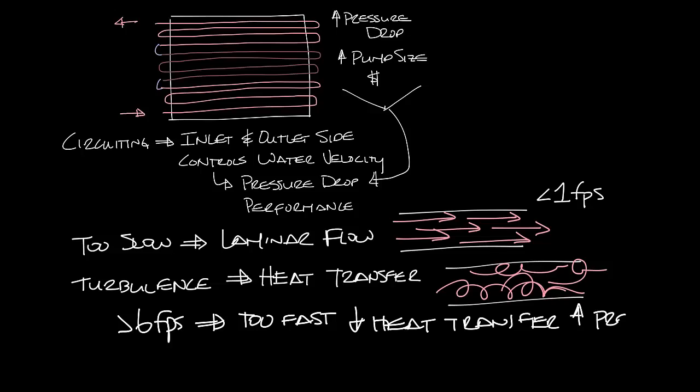This also significantly increases the pressure drop across the coil. So ideally you'd have between one foot per second and six feet per second velocity through your water coils.